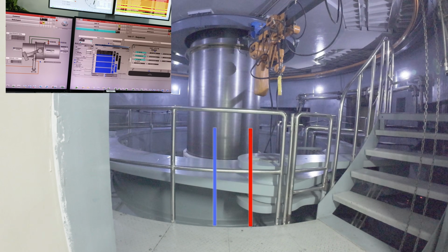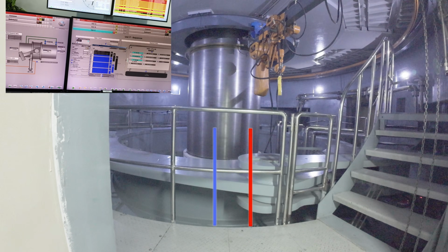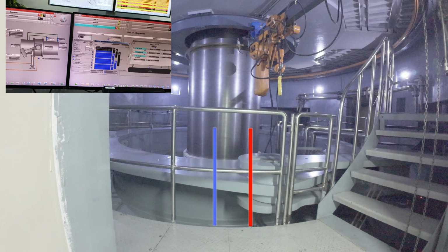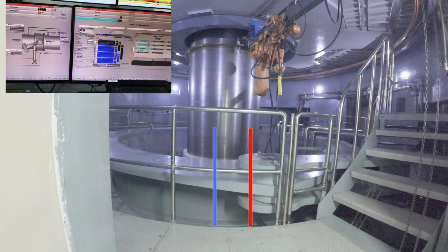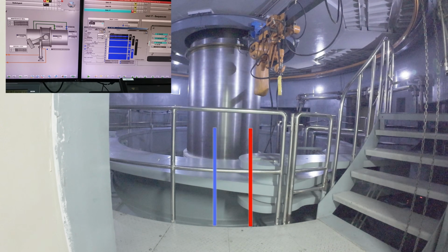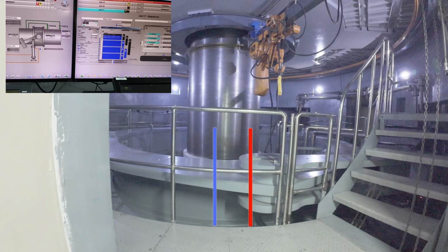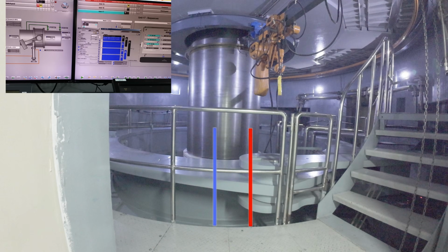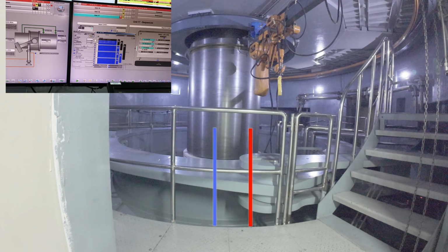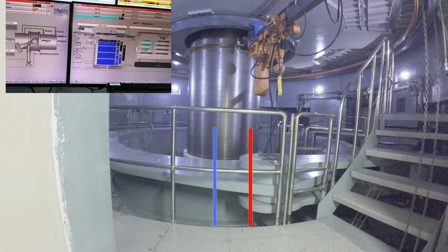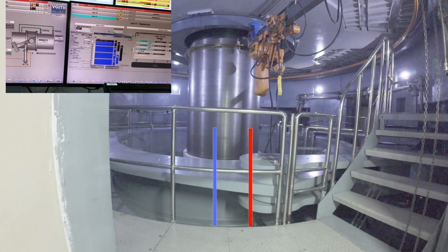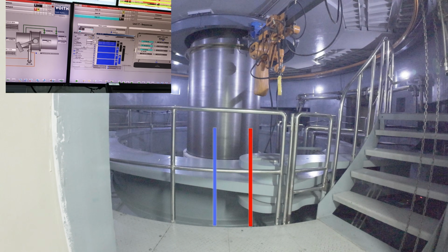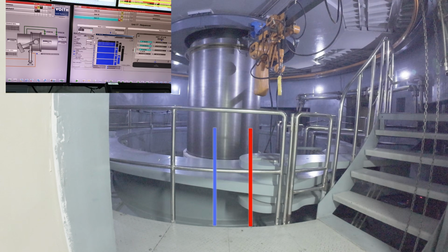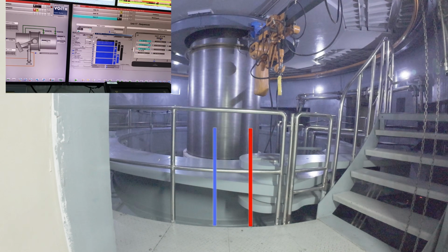And many viewers notice messages and alarms appearing on the control screen. At first glance, it can look like something is going wrong, but most of them aren't warning alarms. They are simple notifications. The system is reporting that pumps have started, valves have moved, cooling systems are running, protection systems are active. Think of it like a checklist. The plant is confirming that each part of the startup process is working correctly. Now the turbine is spinning at full speed, but it still isn't generating electricity for the grid. One final step remains: synchronization.